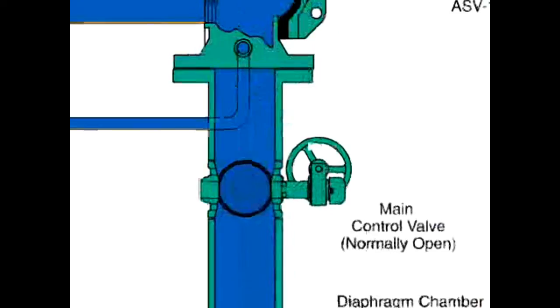To reset the valve after the fire is under control, the main supply valve is manually closed to shut off the water supply, and the diaphragm chamber supply valve is also closed.